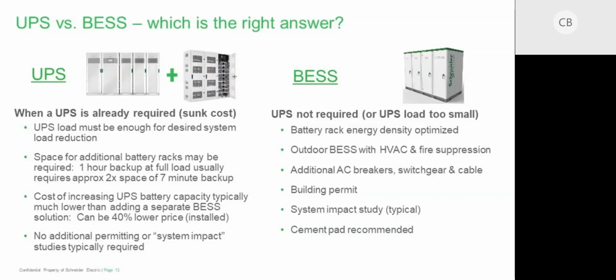Typically, in the co-location industry, it may be 5 minutes. In the financial world, they're pretty risk averse. They may have 10-minute or 15-minute battery runtime. So you've already got this sunk cost and this capital investment that's not being utilized. And today, lithium-ion batteries, with the number of cycles that they can run through, are not susceptible to the wear and tear like a VRLA battery system. They're ideally suited for this solution.